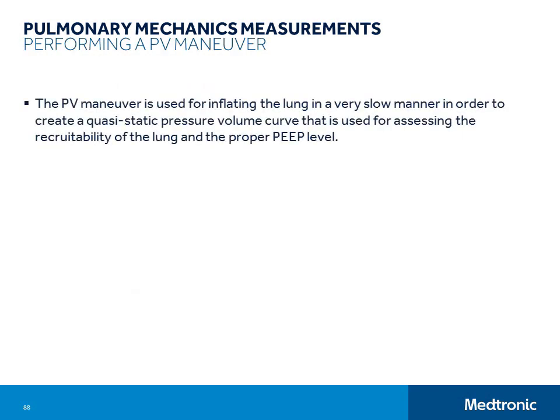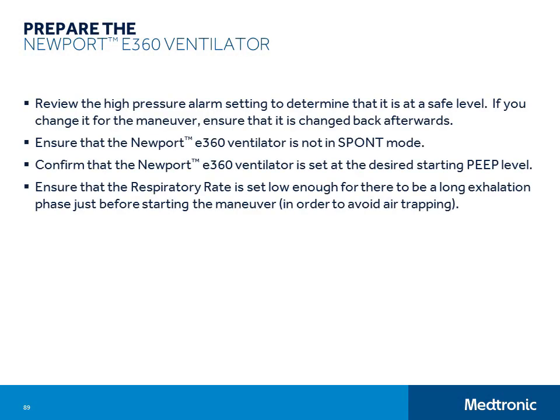Ensure that E360 is not in the SPONT mode. Confirm that E360 is set at the desired starting PEEP level. And ensure that the respiratory rate is set low enough for there to be a long exhalation phase just before starting the maneuver in order to avoid air trapping.